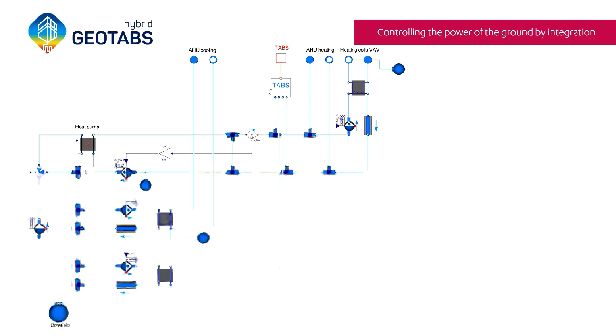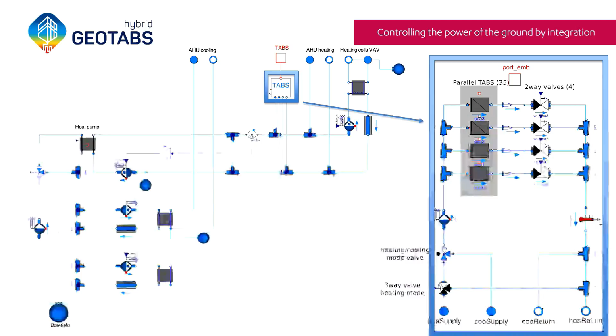Here again we have more information about the concrete core activation. For the 4 floors, we have 1 valve each controlling the flow rate for that floor, and 1 central pump with some valves for mixing between the heat and cooling circuit. Based on this information and these hydraulic connections, the MPC figures out what its control options are, and fully automatically computes the optimal control settings.